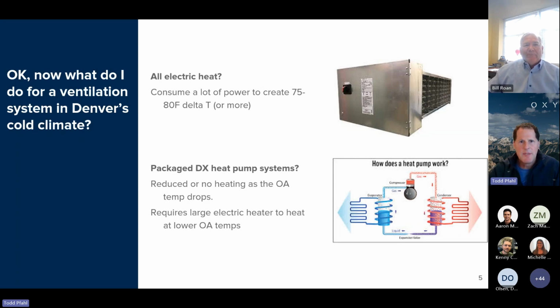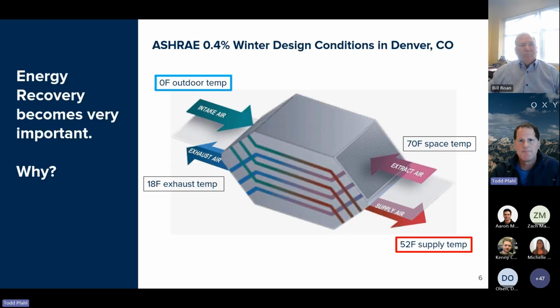A more efficient way to do this is to utilize heat pump technology. So heat pumps are inherently more efficient. However, they tend to reduce in capacity as your outside air drops. Heat pump technology is definitely getting better, and we can see improvements all the time. You'll probably see that if you're going to AHR this year, a lot of improvements there. But a lot of the times, because we have this reduced capacity at low outside air temperatures, we can't get the delta T across that heat exchanger. We can't get the rise of the outside air temperature that we're looking for. So a lot of times we have to add in some supplemental heat, strip heaters, which again sort of reduces the overall efficiencies of heat pumps.